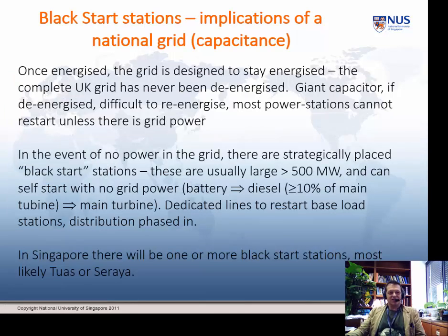Okay, final couple of slides. There's a couple of implications about a grid. They're designed to stay energized. The UK national grid has never been de-energized since the 1890s when it was first put together. It's a giant capacitor, which is why people get killed every year climbing 400 kilovolt pylons when there's no current flowing. They are capacitors, and the person on the pylon provides a route to Earth.